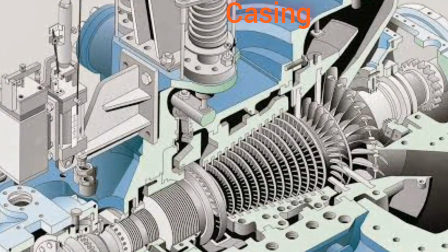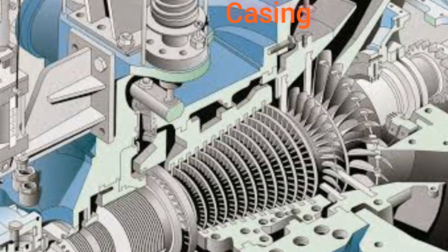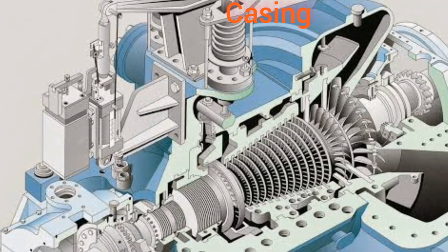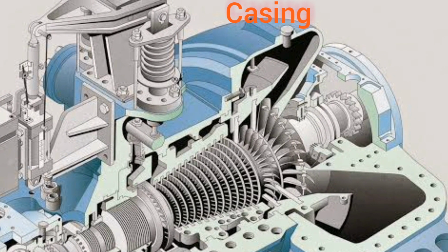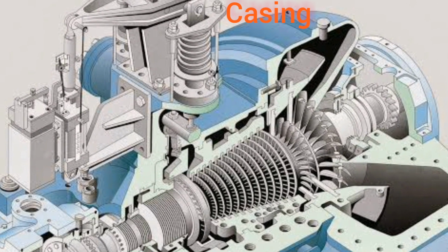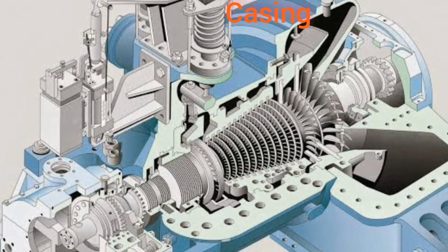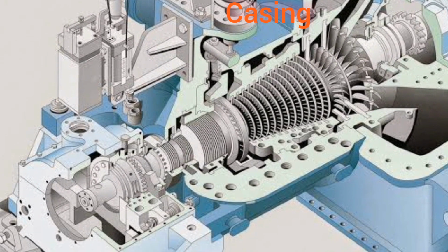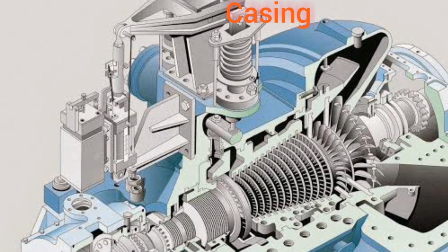Turbine casing. The turbine shape and construction details depend on whether it is a high pressure or low pressure casing. For low and moderate inlet steam pressure up to 120 bar, a single shell casing is used. With a rise in inlet pressure, the casing thickness has to increase. Handling such heavy casing is very difficult. Also, the turbine has to be slowly brought up to the operational temperature. Otherwise, undue internal stress or distortion to the thick casing may arise.